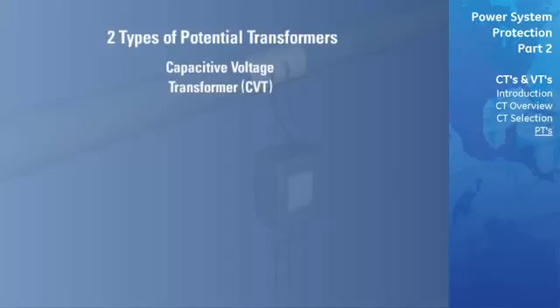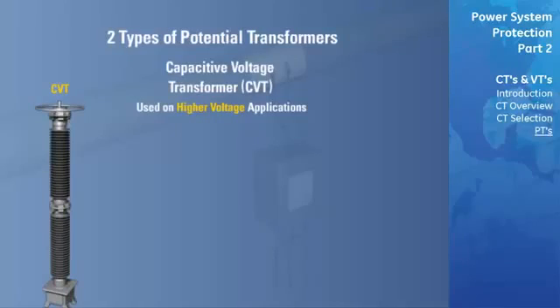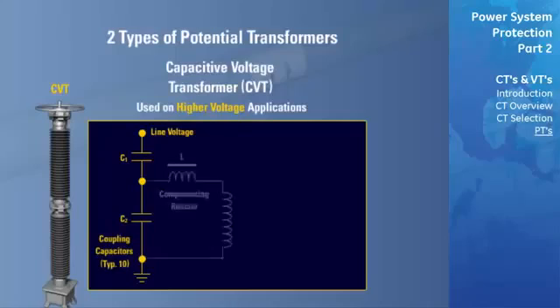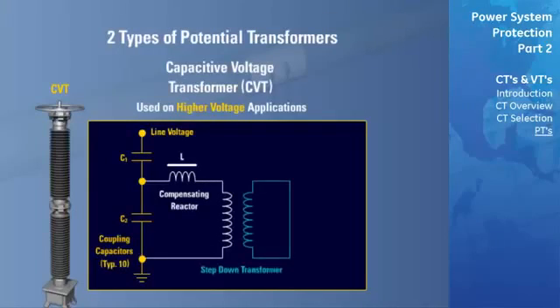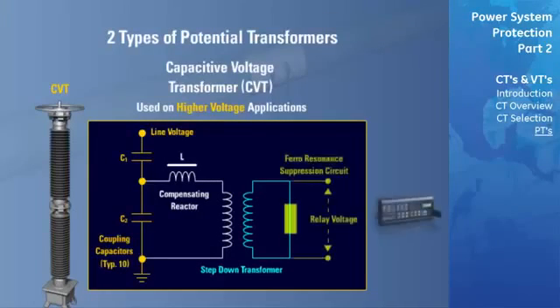Capacitive voltage transformers, or CVTs, are normally used on higher voltage applications. The CVT is basically a capacitance potential divider and consists of the following components: coupling capacitors, typically 10; compensating reactor; step-down transformer; and a ferro-resonance suppression circuit that is found just before the output terminals for connecting to a relay.